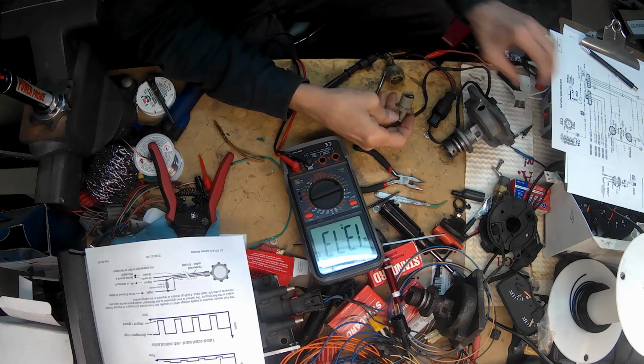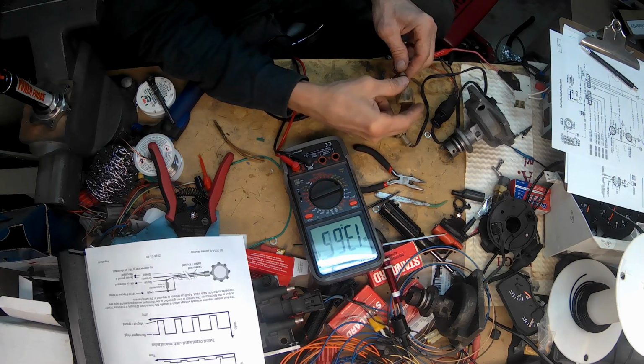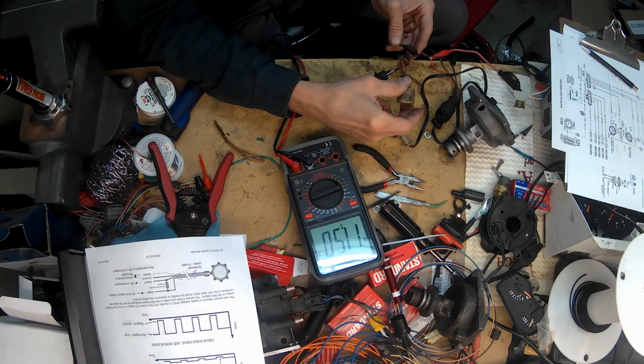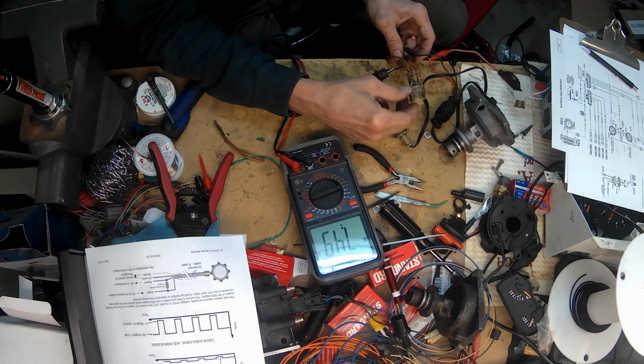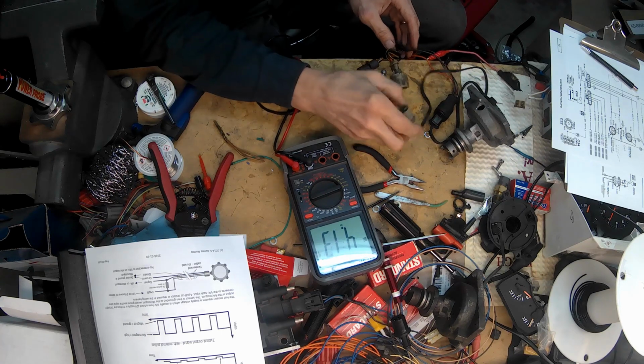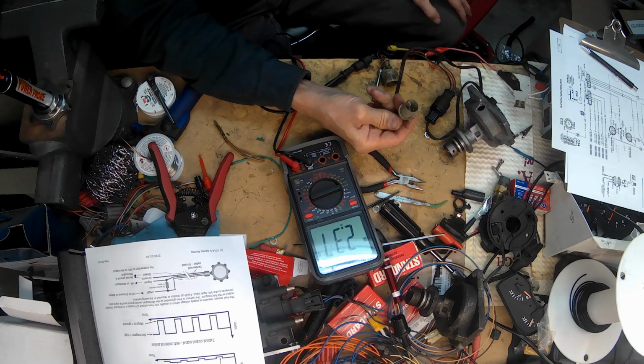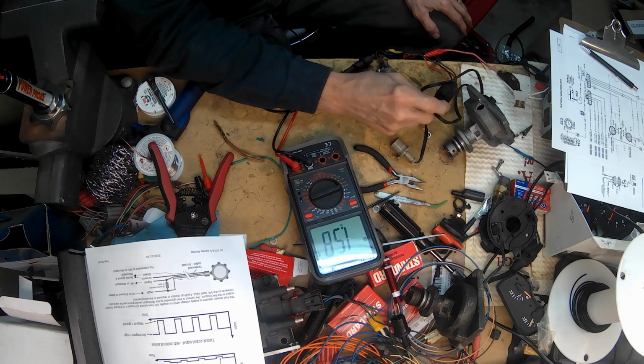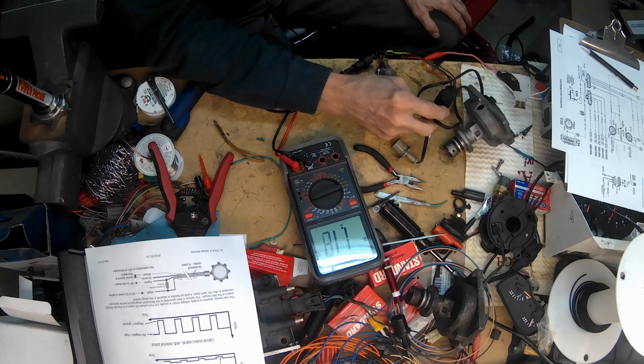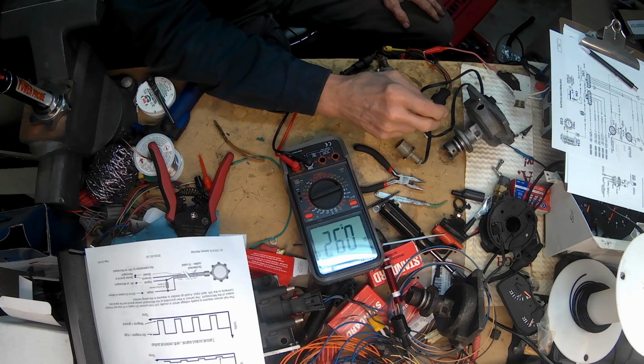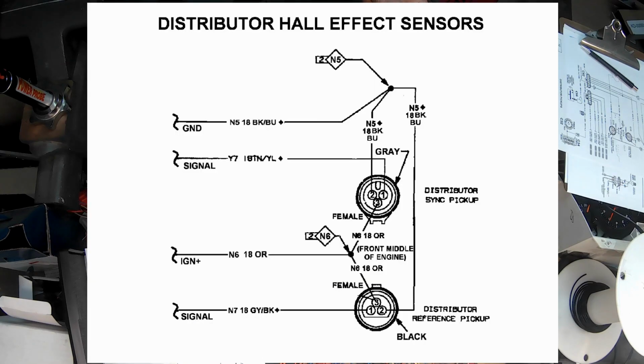One thing I wanted to verify is that if you wire these sensors backwards, in other words the plus would go on the black, blue, and the minus would go on the orange, you'll end up burning out the sensor. So I just did that to the gray connector, and I burned out the sensor for it. But that didn't affect anything, I had the other sensor unplugged, so it's still fine. I hooked that up normally, and I'm still getting my normal signals. But be sure you do not wire these backwards. The positive wire is going to go on the orange, and the negative wire is going to go on the black, blue. And then your signals are going to be your gray, black, or your tan, yellow, depending on which color connector you're using. So hopefully that saves somebody from ruining a good sensor.